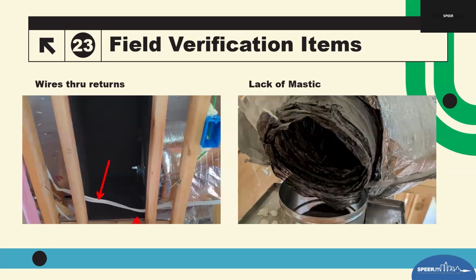Field verification item still, wires running through returns. That to me, whether it's a fire hazard or not, whether the fire marshal will call it out or not, I'm not really sure. If anybody's familiar with the wiring that we see here, when it does, or if it does overheat or smoke, it does produce toxic chemicals that actually now will make it back in the return. So really not a good idea to go through returns. You see the red arrow at the very bottom. That's showing that the return box has been lifted up to allow wire to go under it. Really should just go around it. I don't know why they didn't allow enough wiring to where we could just go around it. There was enough space there. Don't know who was there first, electrician or HVAC, not sure.